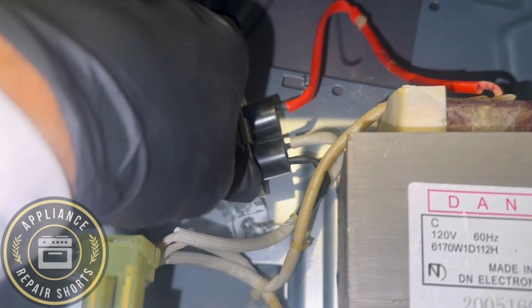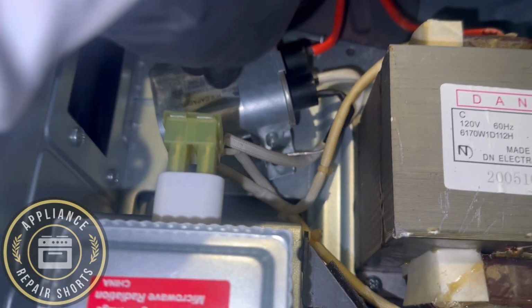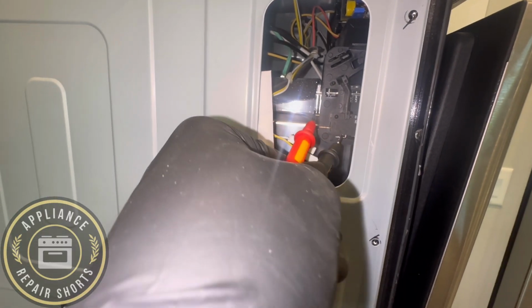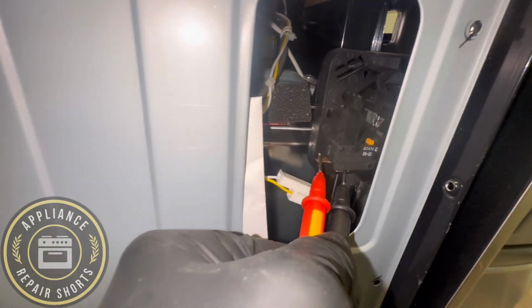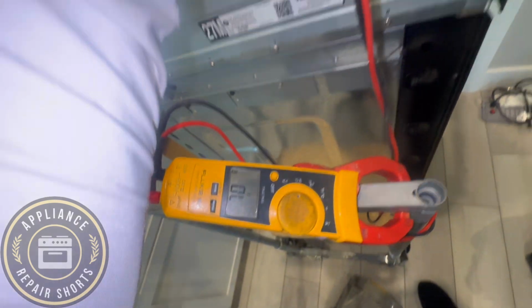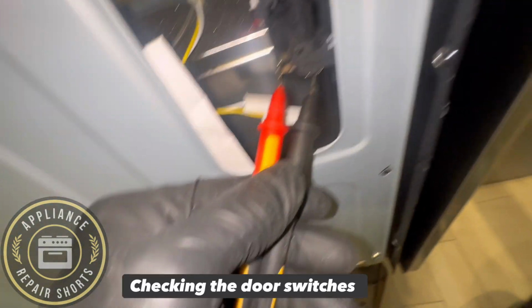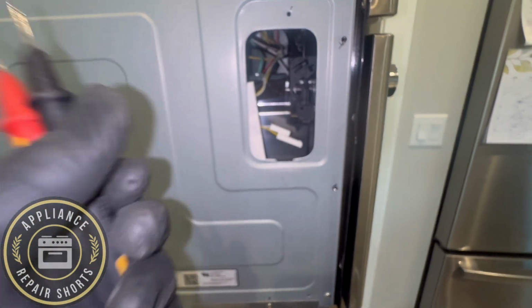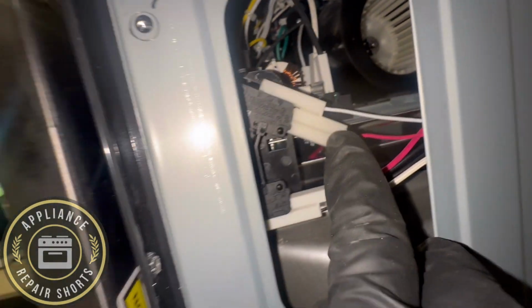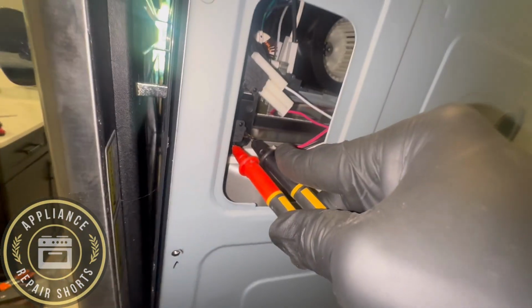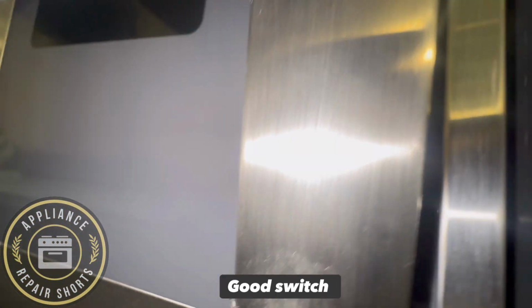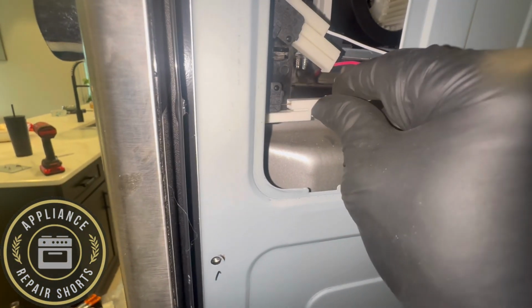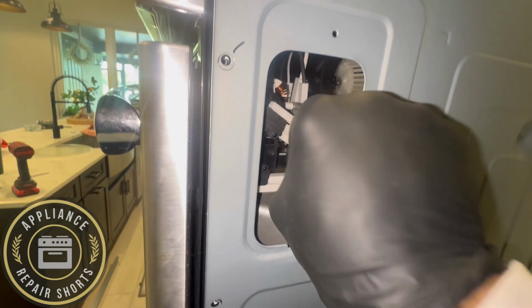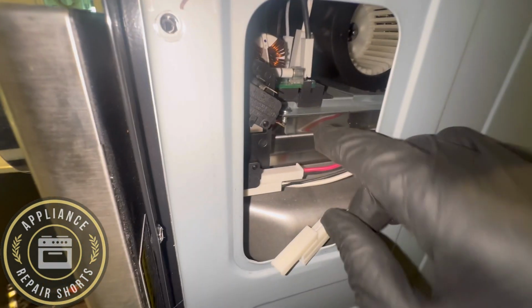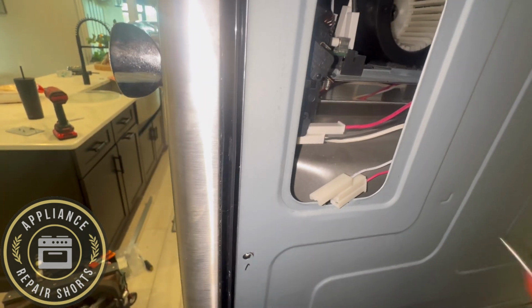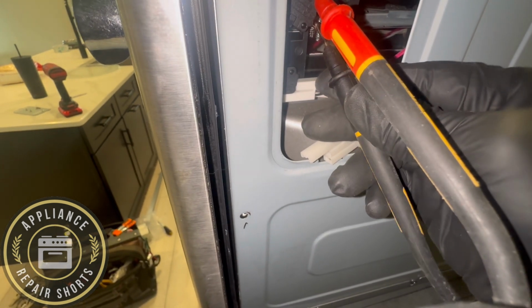Now guys, I know you know this, so make sure the unit is totally unplugged, or in this case, the breaker is turned off. Now we're checking door switches, and just wanted to verify everything is functioning. And you're checking for continuity, and normally depending on the door switch or the door that you're on, you will have continuity with the door open, and when the door is closed, off. All right, so just be mindful of that. But either way, you should get continuity either open or close. If when you're checking one of those switches and you're getting continuity all the time, the switch is bad.